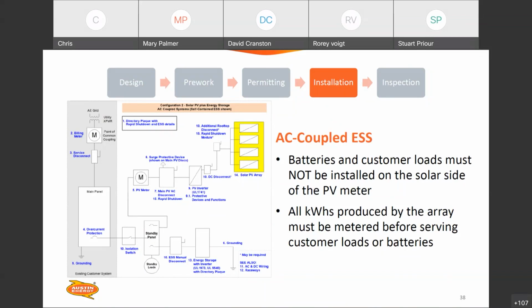So all kilowatt hours produced by the array have to be metered first. If you're going solar array, inverter, aggregate panel, something like that, disconnect, then meter, then interconnection. You can see in the diagram right there basically what I just spelled out for you. Everything's metered. So any load, any battery needs to be on the line side of our solar meter. And that's simply because the solar meter is meant to spin one way, or it takes a read in one direction, not both. All right, next slide.